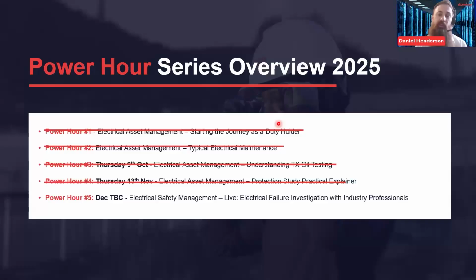And then the last session that we did was looking at protection studies, looking at the coordination, fault levels, and then incident energy analysis for arc flash, and how they all interact, changes that you can make, mitigation, and then how the outputs of those impact the electrical safety of people on your network.